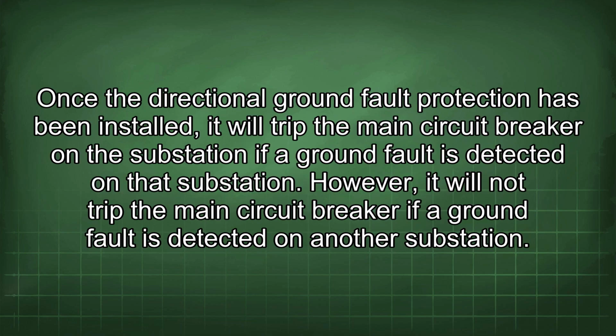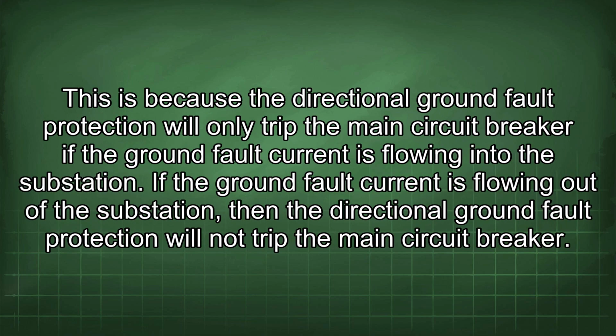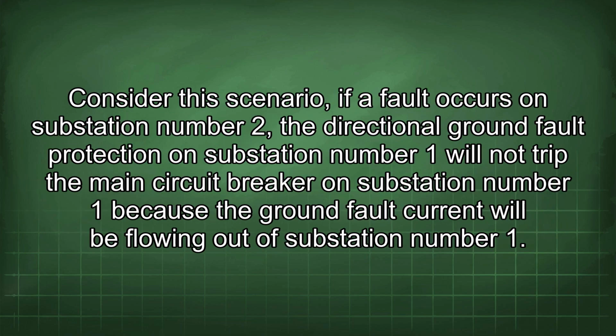Once the directional ground fault protection has been installed, it will trip the main circuit breaker on the substation if a ground fault is detected on that substation. However, it will not trip the main circuit breaker if a ground fault is detected on another substation. This is because the directional ground fault protection will only trip the main circuit breaker if the ground fault current is flowing into the substation. If the ground fault current is flowing out of the substation, then the directional ground fault protection will not trip the main circuit breaker. Consider this scenario.